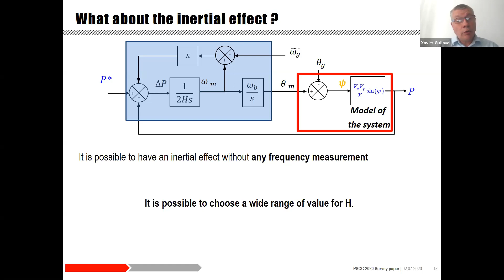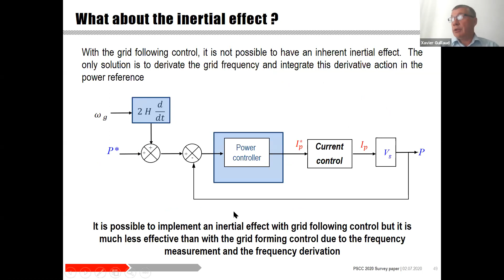With the grid following control, it's not possible to have this inherent inertial effect. The only solution is to derive the grid frequency and integrate this derivative action in the power reference. It's possible to implement this inertial effect with the grid following control, but it is much less effective than with the grid forming control due to the frequency measurement and the frequency derivation. Now let's see how to implement a grid forming control.